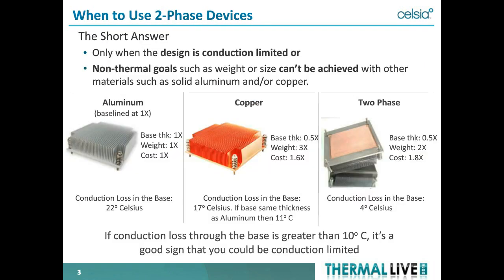When to use a two-phase device? The short answer is always when your design is conduction limited — you're not going to move away from a piece of metal to something else unless there's a reason to, and in this case it's always the conduction limit that's reached. There are other reasons you may want to use it — non-thermal goals such as weight or size, since vapor chamber or heat pipe devices can sometimes be smaller or lighter than an equivalent performance solid material.